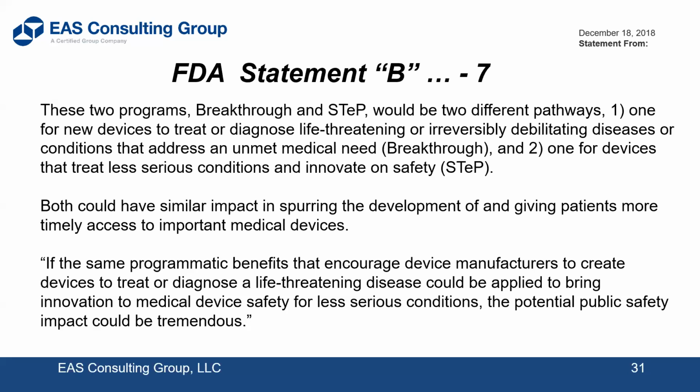A device that can help that, they want to see that quickly get in the market, but they still want to review it. So neither one of these programs replace the 510K or the IDE, Investigational Device Exemption, or the PMA or the de novo. You have to select one of those methods. All this does is give the FDA a heads up. You're going to submit one of these because of life-threatening benefits or safety benefits, and so they'll expedite the review. That's all these two programs do. Expedite the review, even though you're still submitting under what you would normally be submitting, a 510K or a PMA or de novo, and so on.